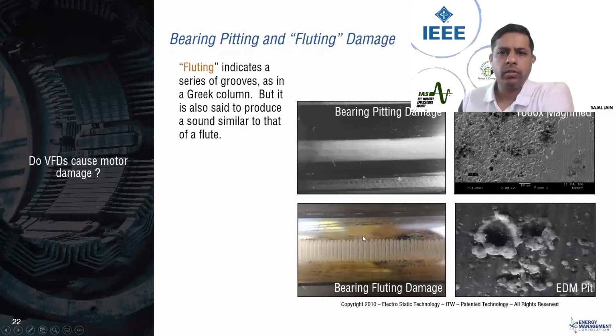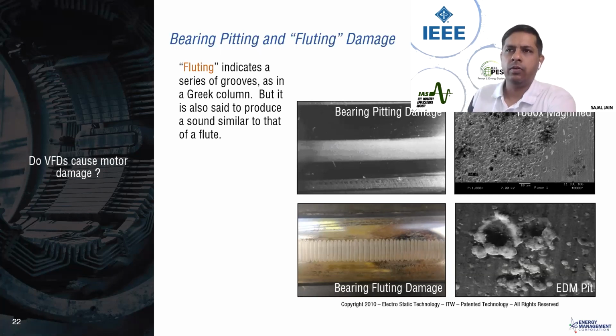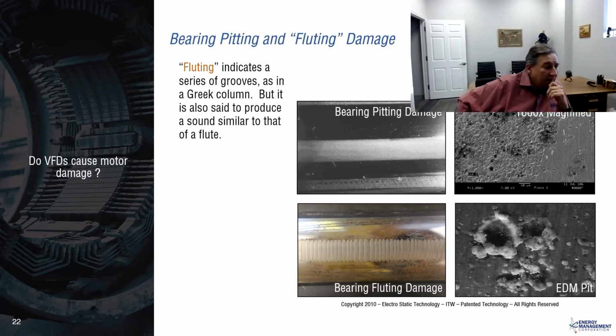A question quickly. Is this only when you have a VFD, or can it happen in a regular motor without a VFD too? That's a great question. Actually, partial discharge and bearing currents are not a new phenomenon with VFDs. Those that have been in the transmission industry with large generators find that they've been putting some kind of mitigation techniques on those large machines, let's say a 2 or 3 megawatt machine, for probably 100 years. And the reason it occurs in those situations is because of eccentricity in the rotor. It'll cause the same kind of issue.